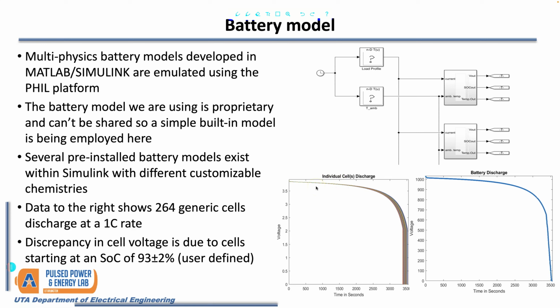Battery cells do not dissipate in a straight line, so 50% capacity does not mean you're at 50% voltage. You'll notice a plateau effect, with a small vertical ramp at the start, and near the end it drops significantly faster than in the middle. All these cells start at 93 plus or minus 2%, so at the top end you might not see that your cells are out of balance except for that tiny ramp at the start. Near the end, when cells are almost dissipated, that same small percentage difference has a huge effect, 2 or 3%, on the cell voltage. This shows the importance of the BMS, since a small percentage point of SOC can have exponential effects at the end of discharge.